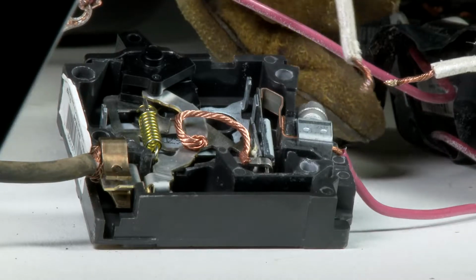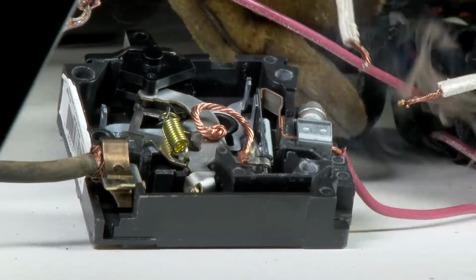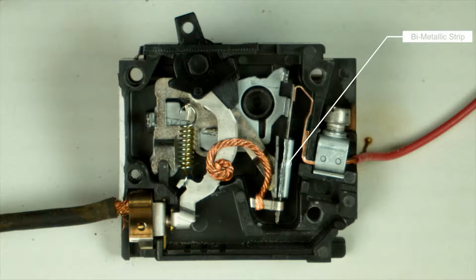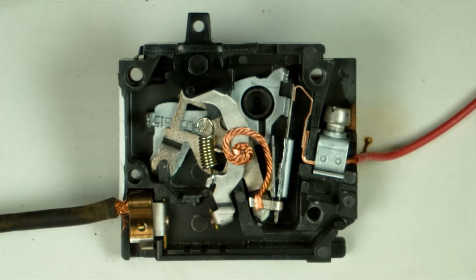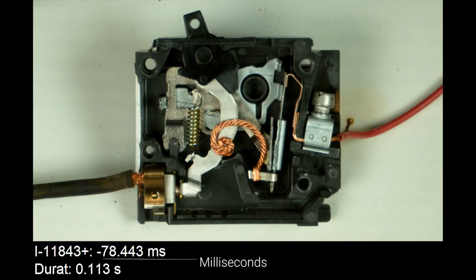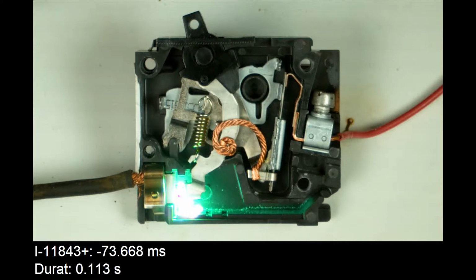Now, in a short circuit condition, this breaker does something pretty amazing. There's so much current passing through that strip, it creates a strong magnetic field that pulls that lever open almost instantly. I found it mind-boggling how fast this actually happens. And if we look at the image data, we can see that the entire event took a mere 6 milliseconds.